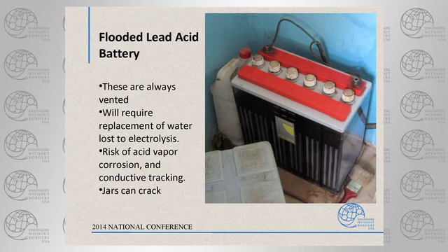And you've also got a wonderful problem of conductive tracking, because the battery electrolyte is electrically conductive. When it collects from a leak or from venting of one of these cells, it can be conductive. And in this case, we've got a wonderful developing situation. It's sitting on a board or a piece of tile. Oftentimes these will be on a metal rack. Depending on the situation, that metal rack may or may not be tied into an electrical ground of the system. Quite honestly, on low voltage systems, it's better to let the thing float, where the batteries aren't tied to the ground of the frame for the batteries.